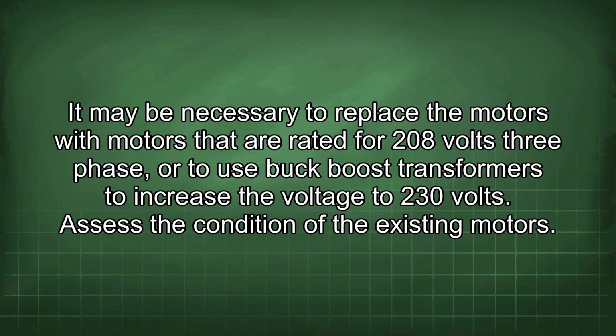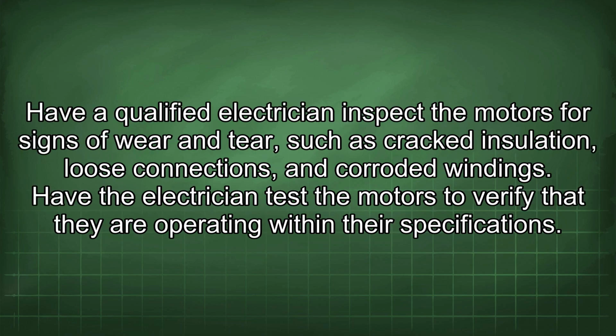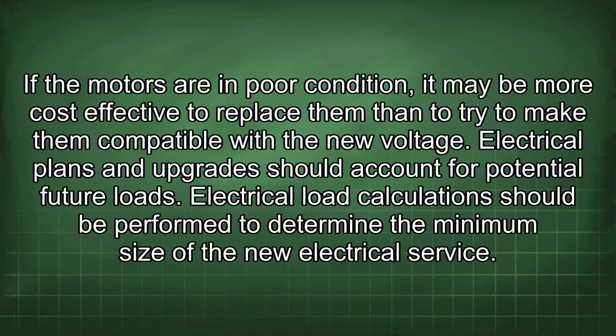Assess the condition of the existing motors. Have a qualified electrician inspect the motors for signs of wear and tear, such as cracked insulation, loose connections, and corroded windings. Have the electrician test the motors to verify that they are operating within their specifications. If the motors are in poor condition, it may be more cost-effective to replace them than to try to make them compatible with the new voltage.